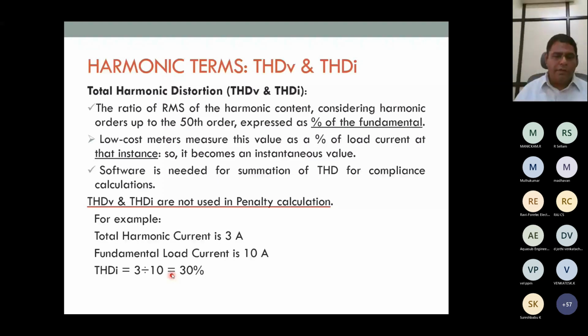So the regulations have been changed. Standards have taken effect, changing all these things. And right now, what we have to measure is the TDD. For voltage, it will be THD, that is total harmonic distortion for the voltage, which is expressed as a percentage of the fundamental. So many people will be having low cost meters in their installation.